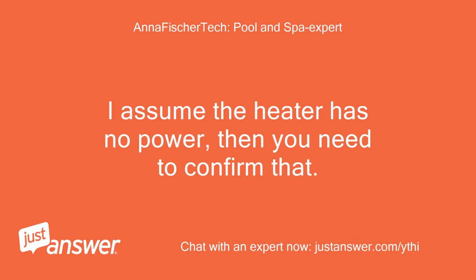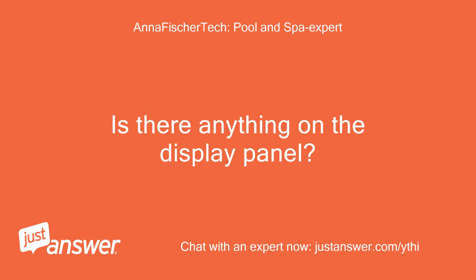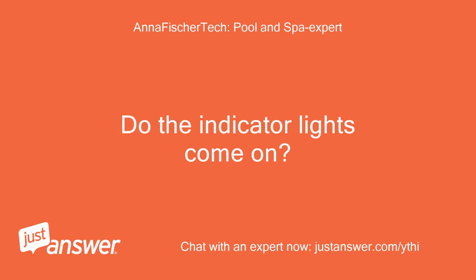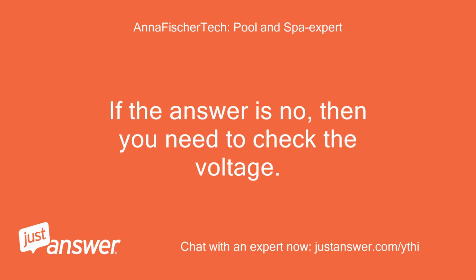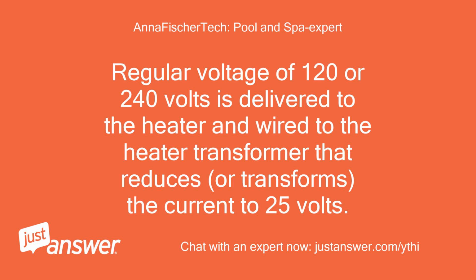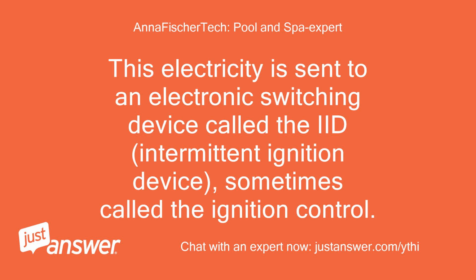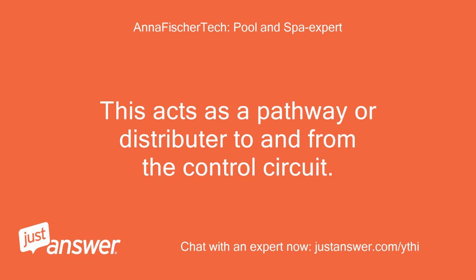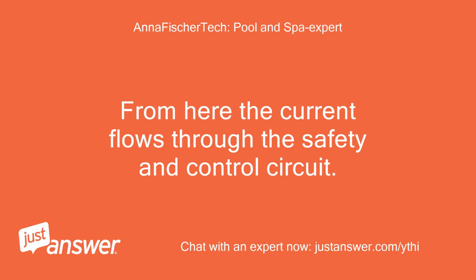I assume the heater has no power, then you need to confirm that. Is there anything on the display panel? Do the indicator lights come on? If the answer is no, then you need to check the voltage. Regular voltage of 120 or 240 volts is delivered to the heater and wired to the heater transformer that reduces, or transforms, the current to 25 volts. This electricity is sent to an electronic switching device called the IID, intermittent ignition device, sometimes called the ignition control. This acts as a pathway or distributor to and from the control circuit. From here the current flows through the safety and control circuit.